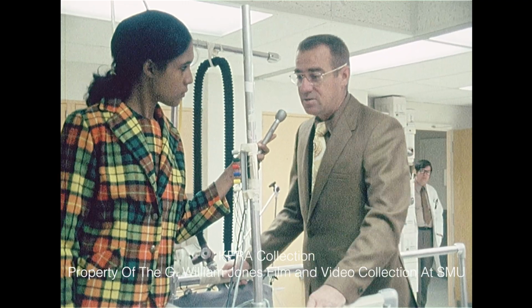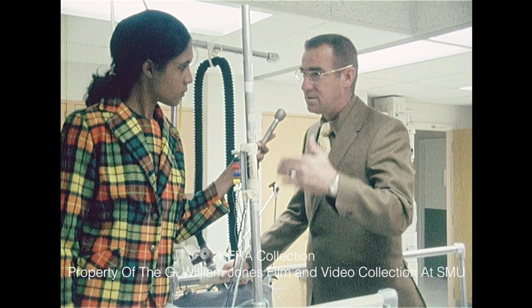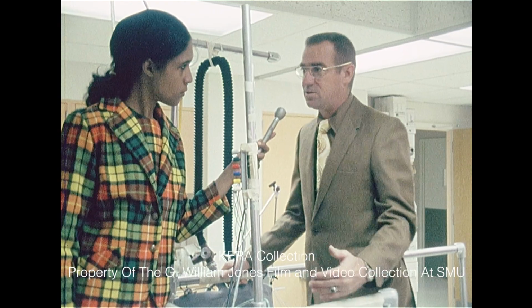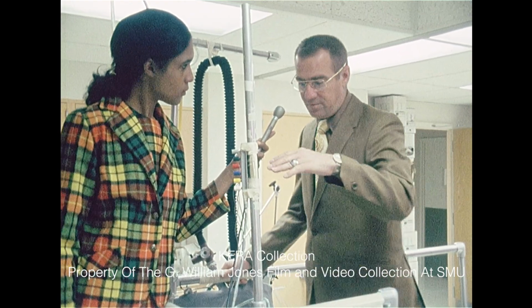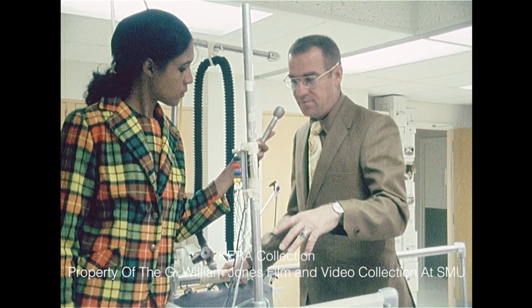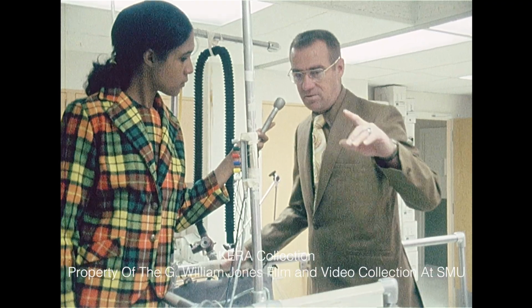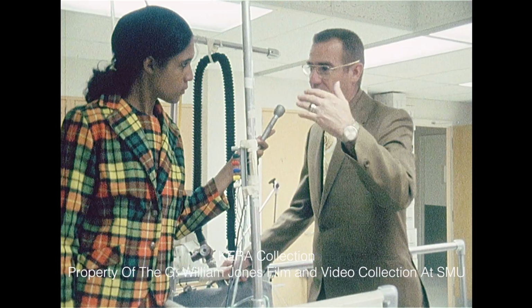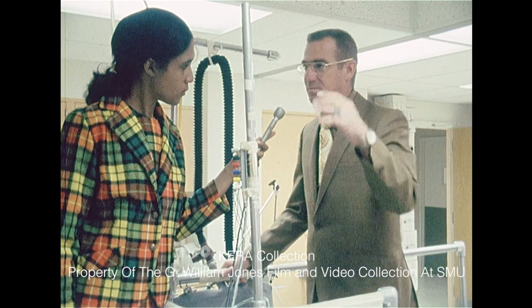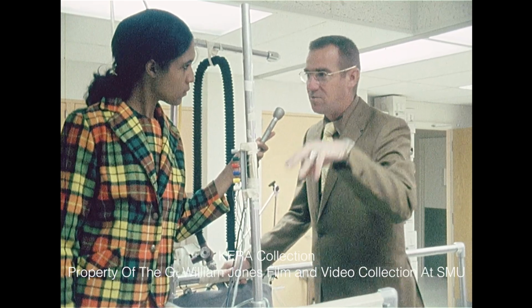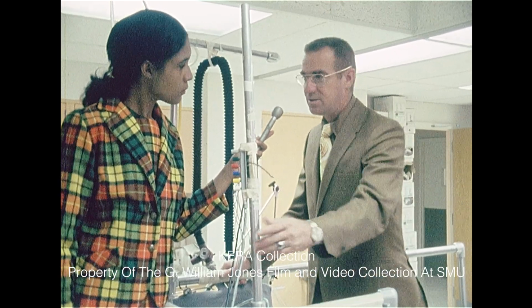In other words, to see that the unit he's getting his ECG off of is in phase with this unit. So what we've done is provide this proper environment—we've assured ourselves that all the plugs in this room are off of the same phase, to keep him electrically in phase with the equipment that he's going to be working with and touching.